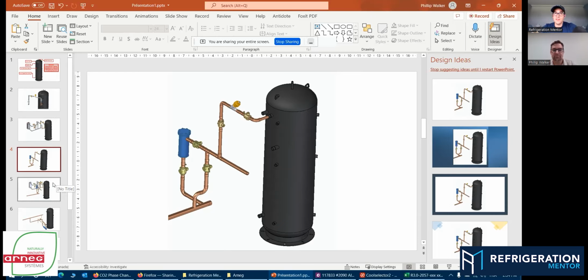But all of a sudden you see they're now running at 70%. You've got to think something's going on. You recognize that. And the more and more technicians I see working on CO2 systems are recognizing patterns like that, because one great thing about a CO2 system is you've got pressure and temperature probes everywhere. And now you can really take a look at the data log and understand how a system's running.